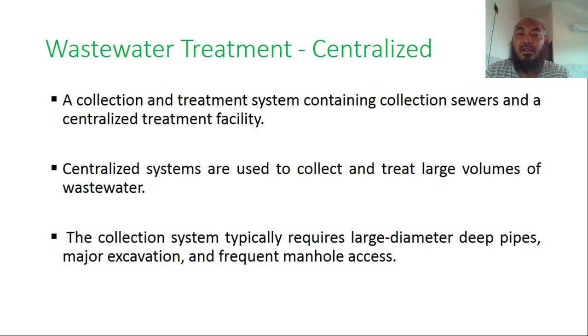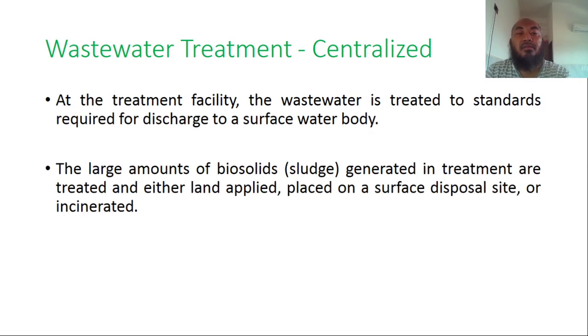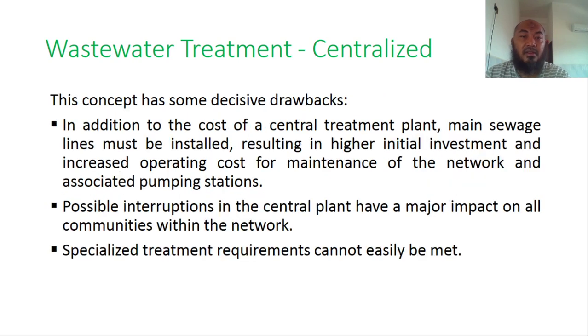The collection and treatment system contains collection sewers and centralized facilities. Centralized systems are used to collect and treat large volumes of wastewater. The collection system typically requires large-diameter, deep pipes, major excavation, and frequent manholes. At the treatment facility, wastewater is treated to standards required for discharge to a surface water body. The large amount of biosolids generated are treated and land-applied, placed on disposal sites, or incinerated.